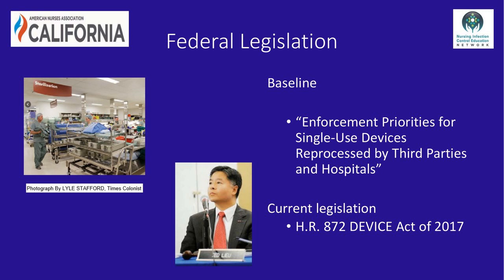Thank you, Aaron. The federal baseline provides a regulatory framework, and this guidance document requires that third-party reprocessors and hospitals comply with all regulatory requirements of the FDA applicable to the original equipment. On the federal level legislatively, Congressman Ted Lieu introduced House Bill H.R. 872 in February this year, called the Device Act of 2017. The Device Act emphasizes that before making any changes to the design or to the reprocessing instruction of a device, the manufacturer shall give written notice of the changes to the FDA. FDA will then assess and analyze and decide if they need safety regulations.